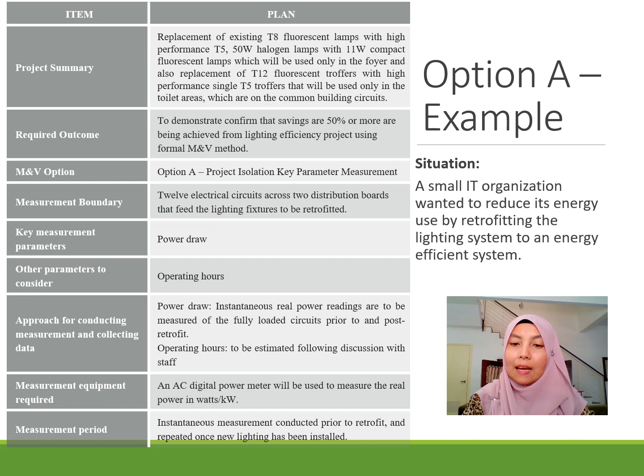So the approach for conducting measurement and data collection. For power draw, instantaneous real power readings are to be measured of the fully loaded circuits prior to and post retrofit, before and after changing the lamp. Operating hours in this case will be stipulated, estimated following discussion with the staff in the building. For measurement equipment, an AC digital power meter will be used to measure the real power in watts or kilowatts. The measurement is an instantaneous measurement conducted prior to retrofit and repeated once the new lighting has been installed.